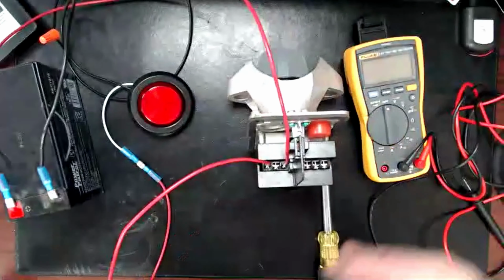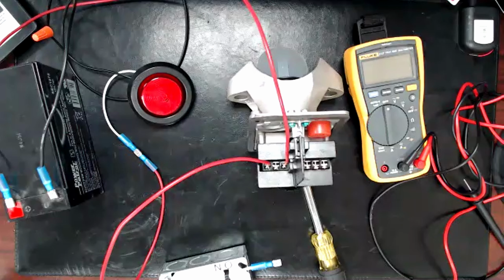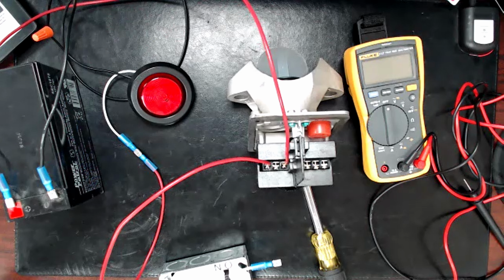Let me see if I can. Yeah, go ahead, the last question before you do that. Now, when we're using the new power supplies and you're programming one of the outputs as a NAC circuit, do you still use the end of line or you don't have to? If it's programmed as a NAC circuit, you still use an end of line. If it's programmed as an auxiliary power circuit, then you do not have to. So that depends on which way it's programmed. And that would be a thing you communicate with the guy doing your programming on site.